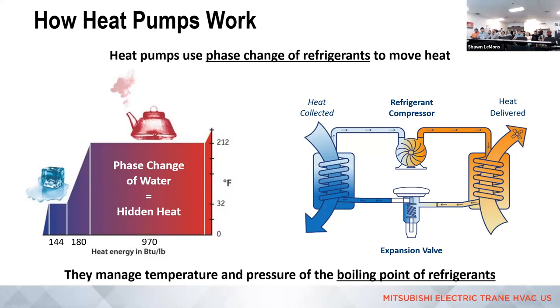As we ramp up from freezing to boiling, there's one BTU per degree, and 180 degrees in that ramp up. But then we get to the boiling of water, and there's 970 BTUs in the change of water from liquid to vapor. Those are hidden boxes of heat, because it's not changing temperature at that point, it's just changing phase. It's that phase change that makes all the difference in how we put steam to work to build our civilization, how we use ice to create cooling - a ton of ice did 12,000 BTUs of cooling, thus a ton of cooling. This phase change is where the magic happens.